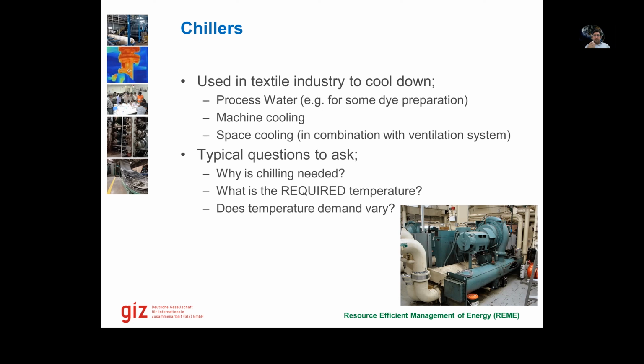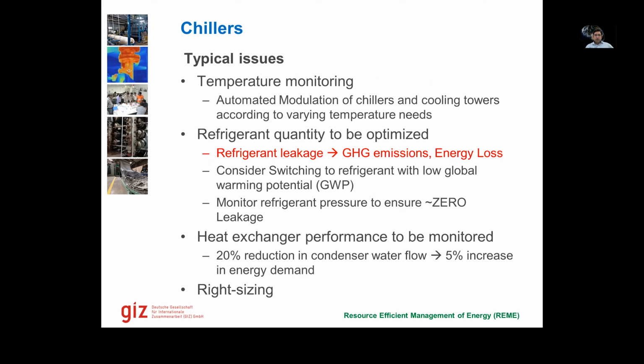For example, what are the temperatures required? If the temperature required is around 25 or 30 degrees Celsius, why are we even using a chiller? Why are we not using a cooling tower? That temperature can be achieved by good cooling towers as well. And then, do the demands vary or not? If the temperature demand on the demand side varies, are we modulating the chillers accordingly or not? So these are typical issues.